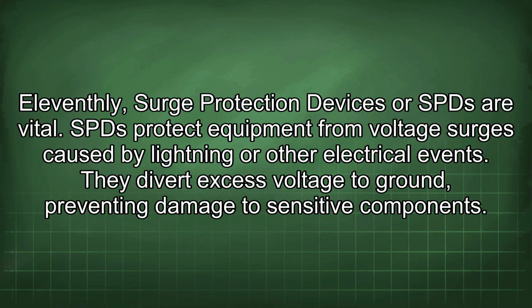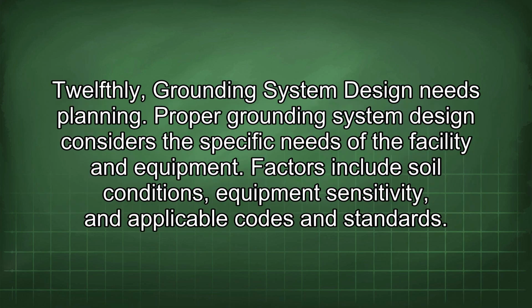Eleventhly, surge protection devices, or SPDs, are vital. SPDs protect equipment from voltage surges caused by lightning or other electrical events. They divert excess voltage to ground, preventing damage to sensitive components. Twelfthly, grounding system design needs planning. Proper grounding system design considers the specific needs of the facility and equipment. Factors include soil conditions, equipment sensitivity, and applicable codes and standards.